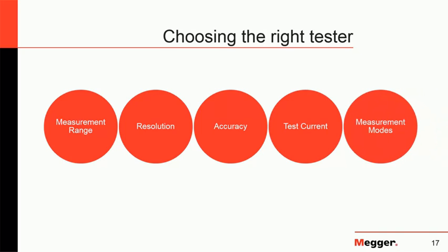And finally, the last factor to consider will be the measurement modes. Those will come into the picture for applications like circuit breakers, for example. We see this in the circuit where it is recommended to run the current in both directions to avoid magnetizing the CTs.